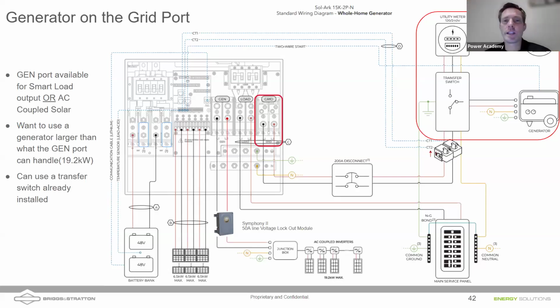Yeah, that's a great question. The answer is yes, right? You do need a transfer switch, right? So you'll need to use a transfer switch, and that's what I'm addressing in this slide here. So if you're going to use that gen port for AC coupled solar, no problem. The one thing you don't want to do, though, the generator typically comes on as those batteries are getting low, right? And so if that AC coupled solar starts to get weak and you're using all that power in the home and the batteries are getting low, but the sun's still out, maybe you've got a small AC coupled array on the roof, you don't want that backfeeding the generator.